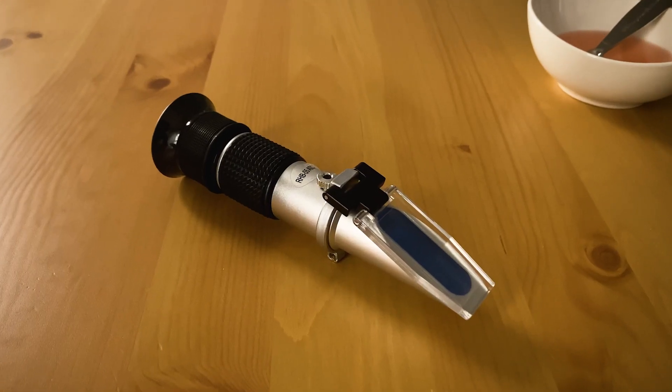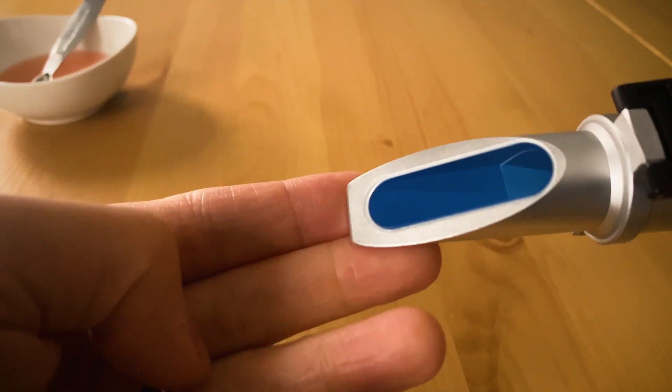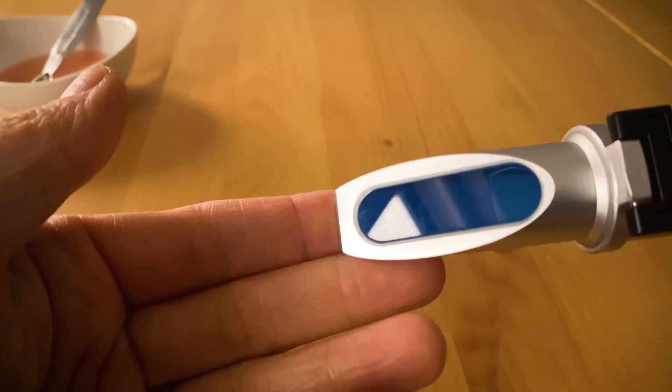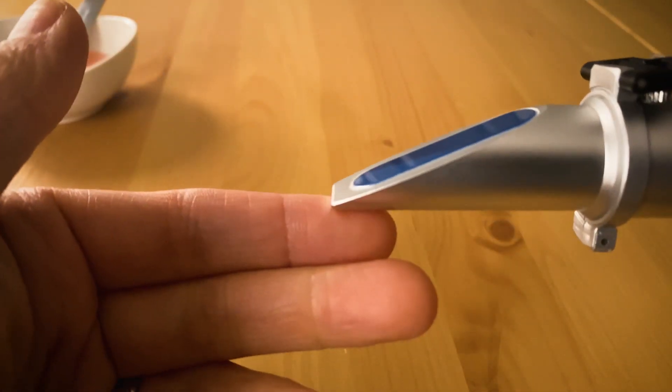Degree Brix is measured with this device here called a refractometer. A refractometer measures the degree that light passes through a solution is bent. Here you see the angle prism in blue. The refractometer measures the angle of light coming in and the angle of light coming out of the angle prism. The refractometer I have has a measuring scale of 0 to 55 degree BRICS, and it's made to measure dissolved sugar in an aqueous solution.